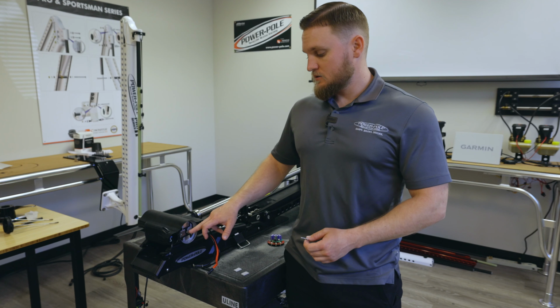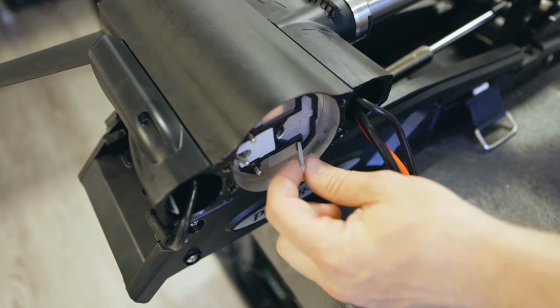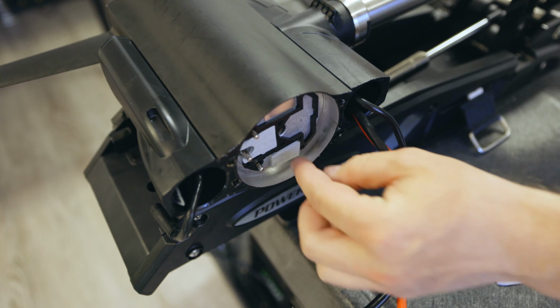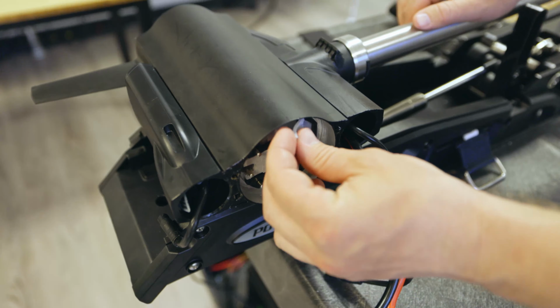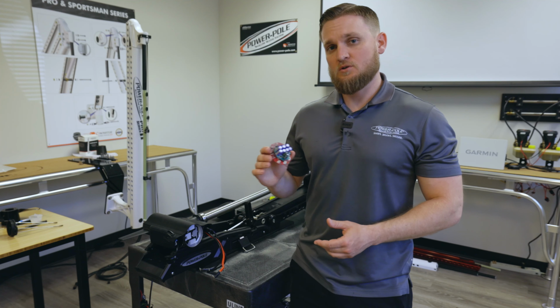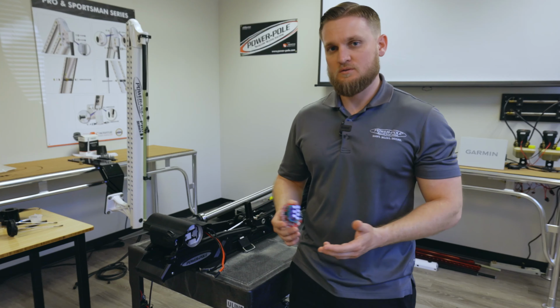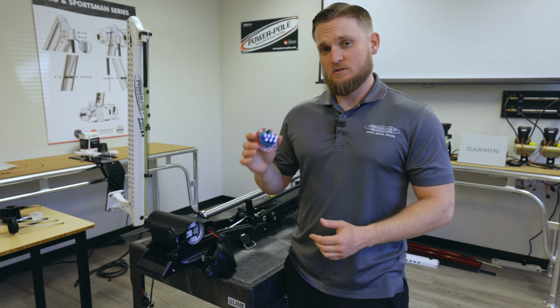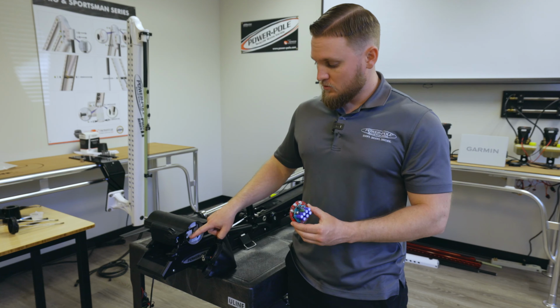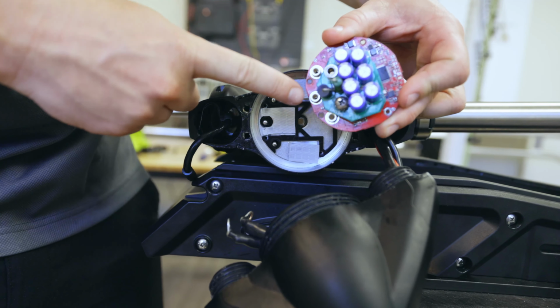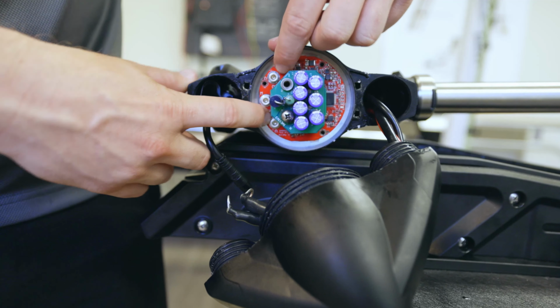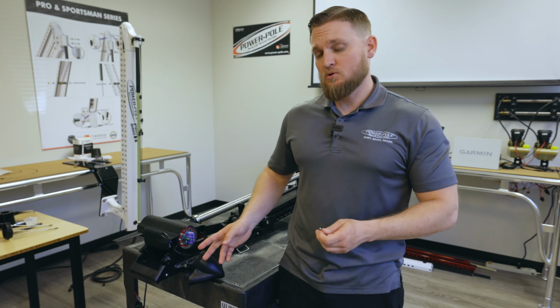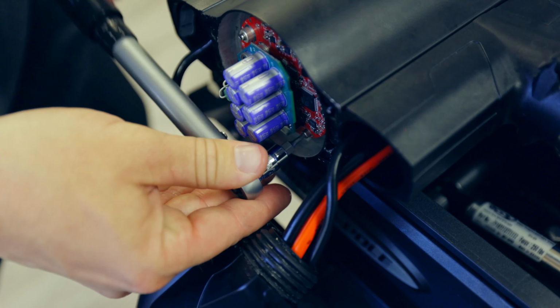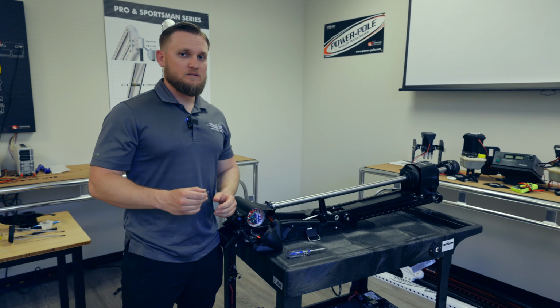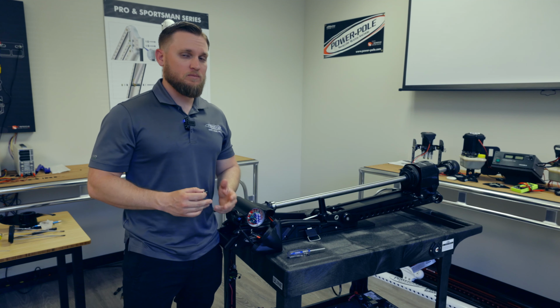Now that we have the spacer frame in place, we can line up our 3 thermal interface materials. These three thermal interface materials are important to have in place as they will help protect the circuit board from any potential overheating issues. Now we are ready to install our propulsion circuit board. Line up your contact ports with the 3 holes that you see at the edge of the circuit board. Now we are ready to secure the propulsion circuit board. Remember to use your torque wrench and to tighten down to the listed torque specs that can be found in the instructions.